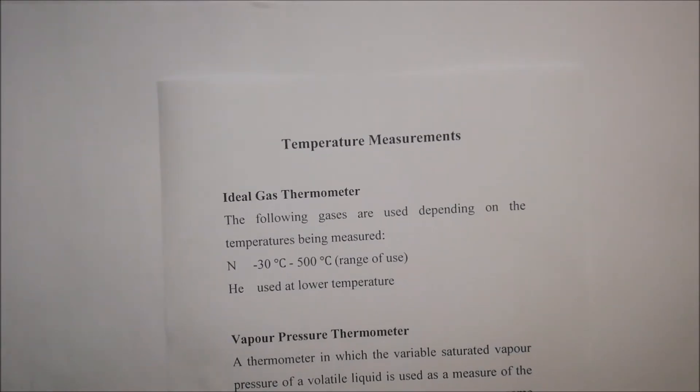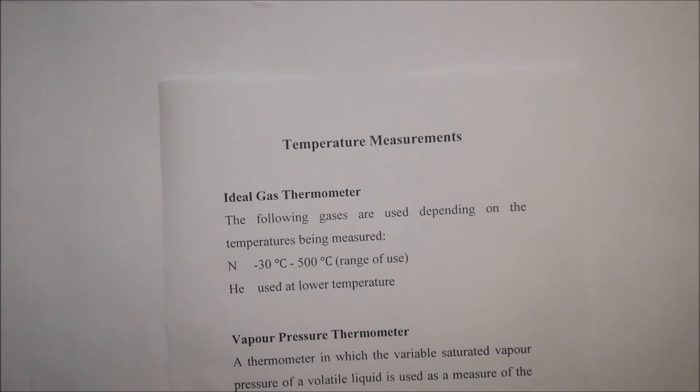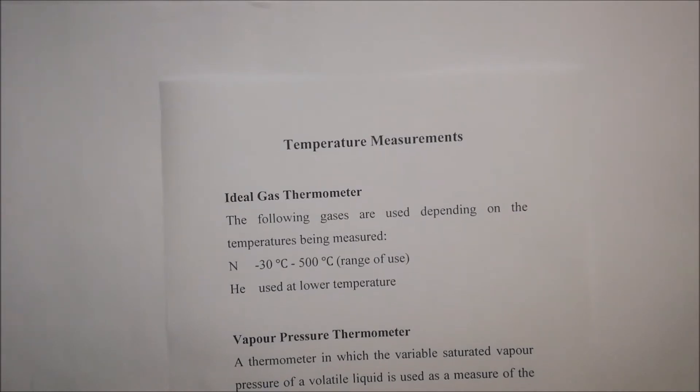The first system we're going to be looking at is the ideal gas thermometer. The following gases are used depending on the temperature being measured. If you want to measure a temperature range from minus 30 degrees Celsius to about 500 degrees Celsius, then you would use nitrogen as the gas. If you want to lower that temperature to less than minus 30 degrees Celsius, then you would use helium.